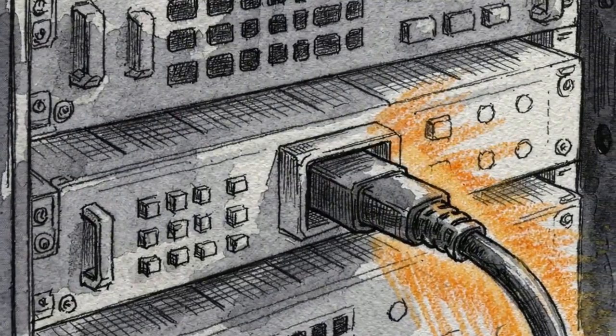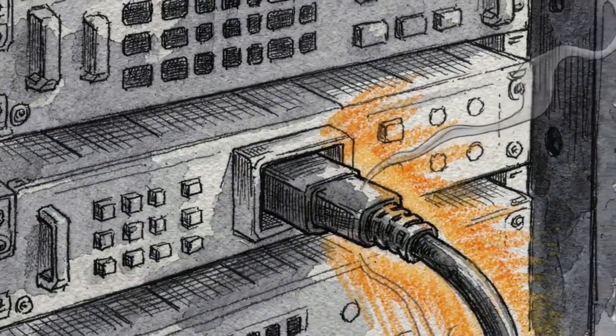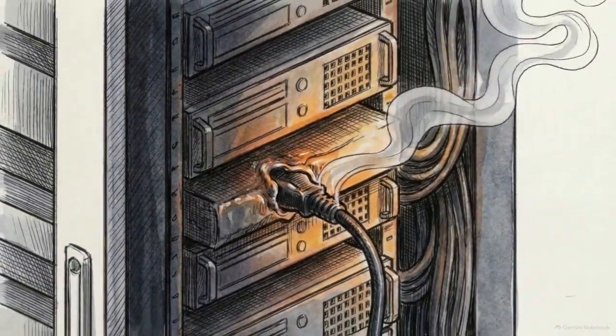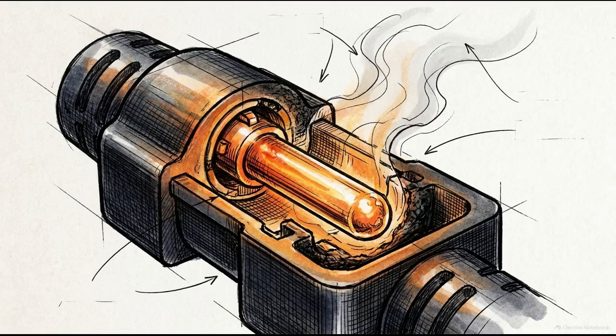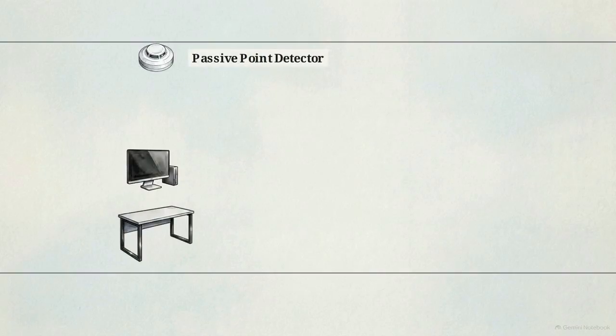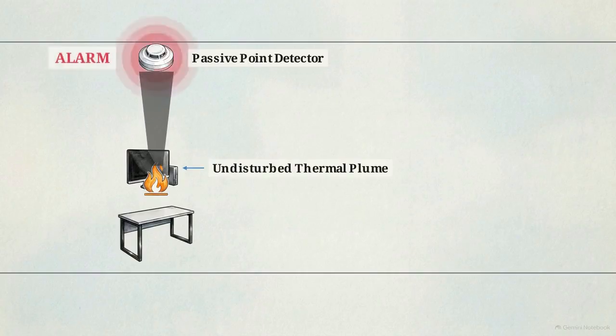Inside a critical facility, the most dangerous thermal events start small. Long before visible flames appear, cable insulation failure or power connection hotspots produce low-density, incipient smoke that is almost invisible to the naked eye. In a standard office environment, detecting this is straightforward. The ambient air is relatively still, allowing the undisturbed thermal plume to rise predictably to a ceiling-mounted point detector.